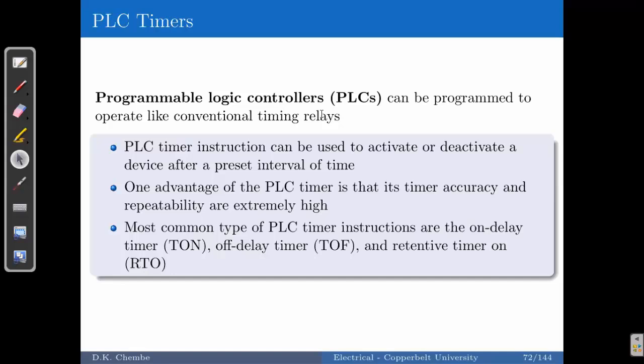PLC timers can be used to activate or deactivate various devices in industry. The advantages of PLCs include that they are very accurate and have high repeatability, meaning they can operate for a long period doing the same sequence or pattern. The most common PLC timer instructions are the on-delay — called TON (timer on delay) — the off-delay timer — called TOF — and a retentive timer called RTO.